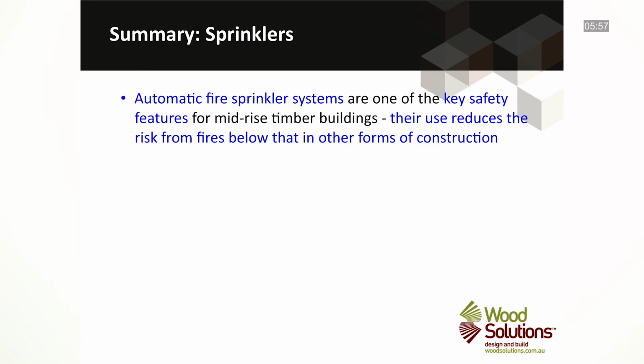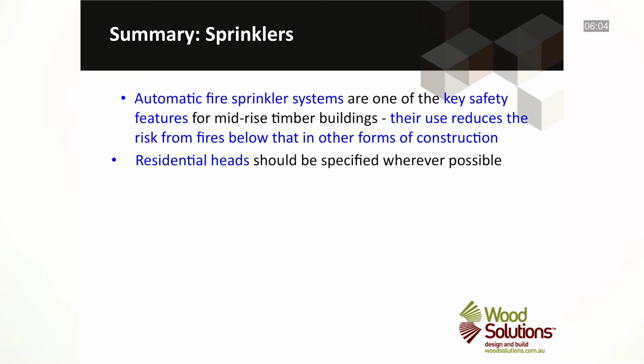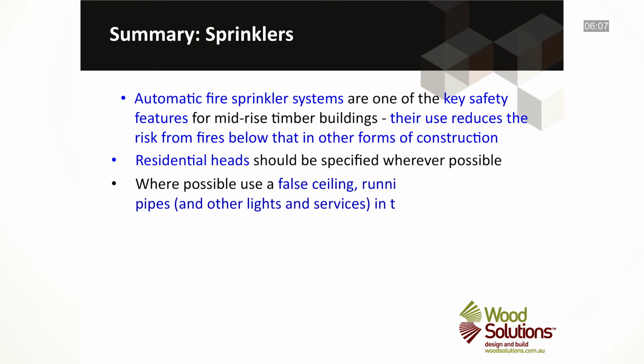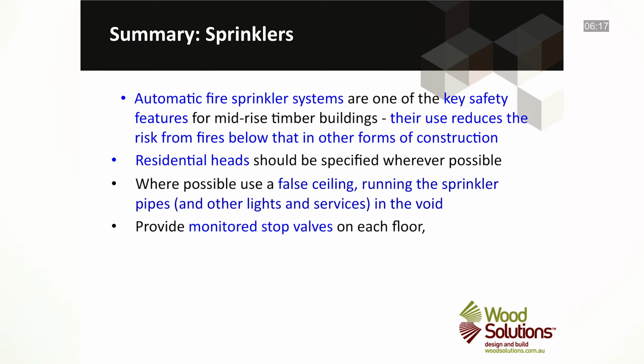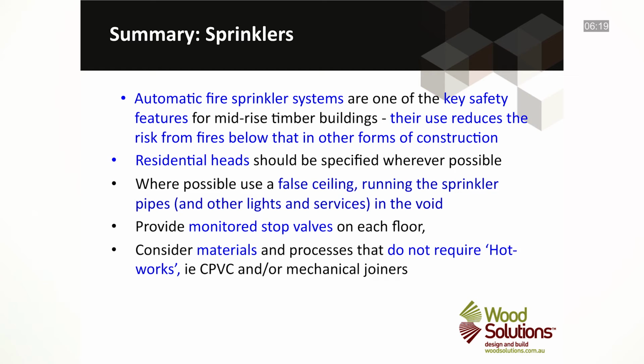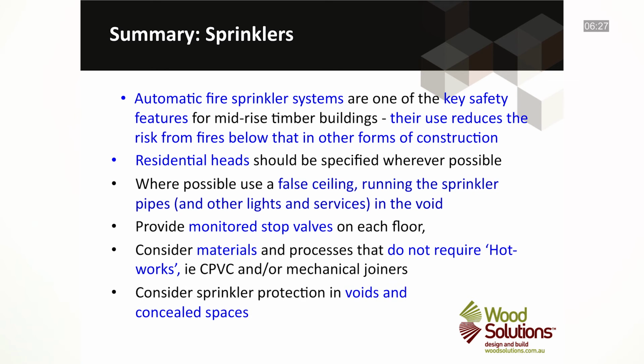So in summary, automatic fire sprinkler systems are one of the key safety features for mid-rise timber buildings. Their use reduces the risk from fires below that of other forms of construction. Residential sprinkler heads should be specified wherever possible. Also, where possible, use a false ceiling, running the sprinkler pipes in the void. This void can then be used for placement of downlights and running of cabling. Provide monitored stop valves on each floor. Consider piping materials and processes that do not require hot works, such as CPVC and/or mechanical joiners. Finally, consider sprinkler protection in voids and concealed spaces.